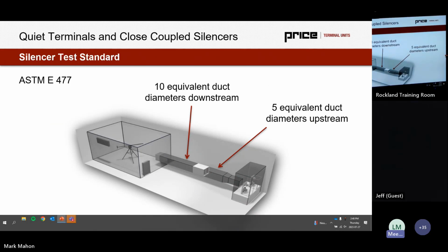When we look at ASTM E477, which is the silencer test method, the way we actually get a catalog insertion loss is we're going to have a known source of sound, which is going to be discharging both air and acoustics down an open piece of ductwork. And we're going to measure that sound power value in a reverberant room. We then replace a section of the duct with a silencer. We measure again, and the difference in measured sound is the insertion loss of the silencer. Does that make sense? So we start with the greater magnitude, measure the lesser magnitude, thanks to the silencer, and characterize the changes of the silencer's performance.